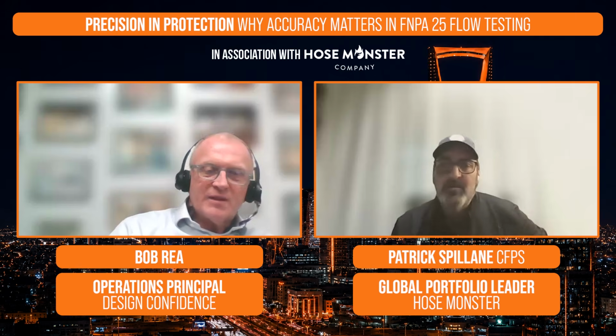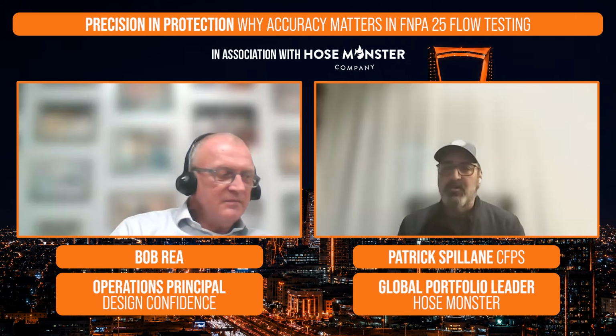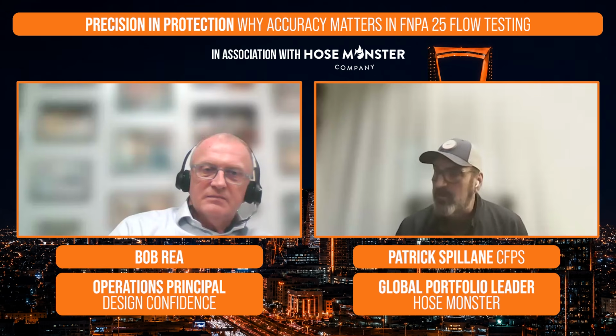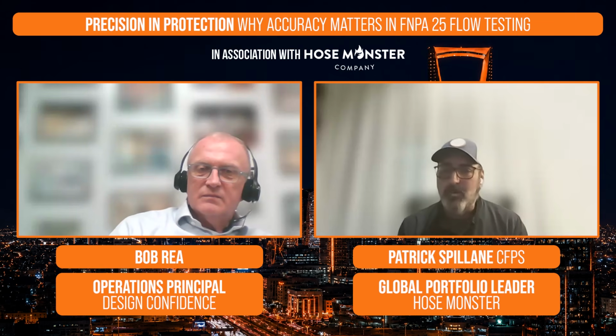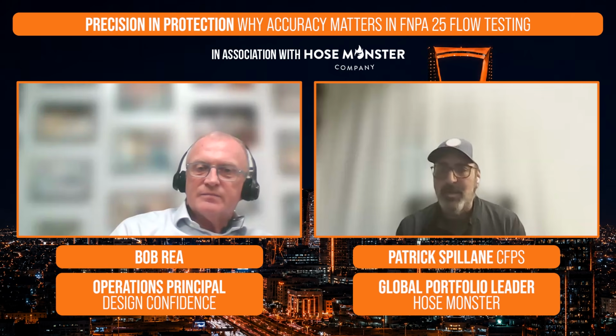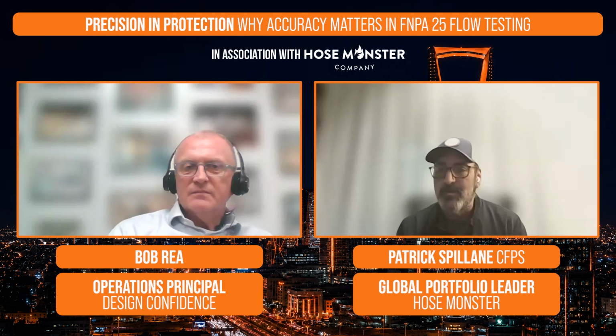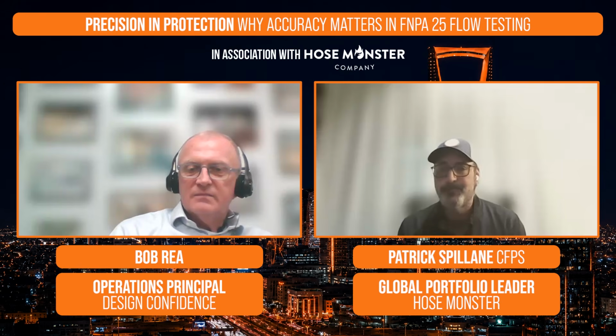It's going to be very similar to that annual flow test. Making sure that the fire pump is working properly per the fire pump placard or the original acceptance test of that fire pump, that it's meeting that same performance. So yes, if that fire pump is taken out of service and you perform any repairs or modifications, or replace any major components that would affect the performance of that fire pump, we want to do a full flow test after that correction has been made to confirm the fire pump is back in acceptable order.